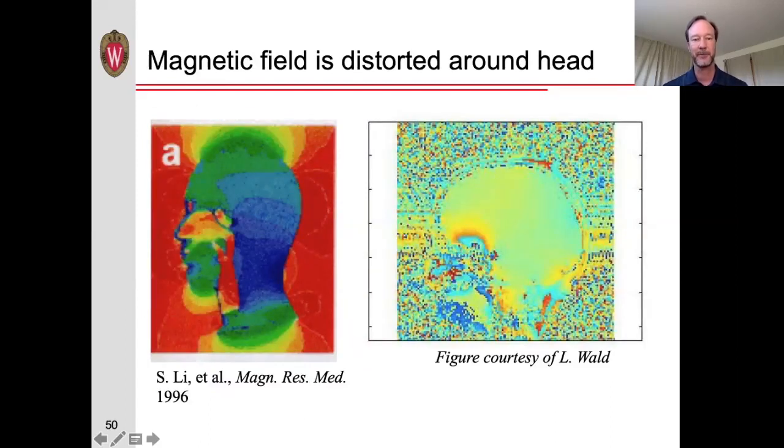Another distortion comes from non-uniformities in the magnetic field. So if we place the head in a magnetic field, the magnetic field is going to become distorted somewhat. On the left is a simulation for what the magnetic field distortions would look like, with the main magnetic field going in the superior-inferior direction. On the right is an actual image of a field map taken from Larry Wald at Massachusetts General Hospital. You notice the non-uniformity particularly here in the frontal lobe, and that results from this air-tissue interface in the sinuses. Because of this difference in magnetic susceptibility between the air in the sinuses and the tissue in the brain, that causes magnetic field non-uniformities that propagate even further into the brain.